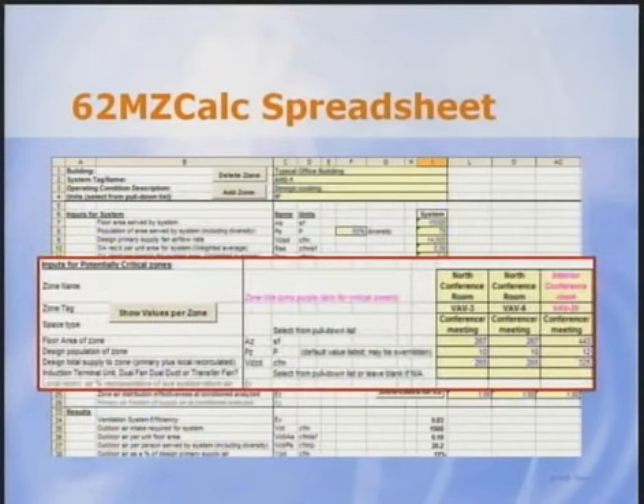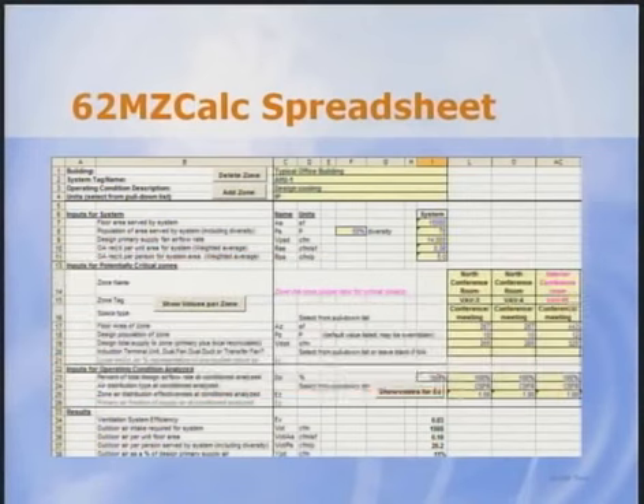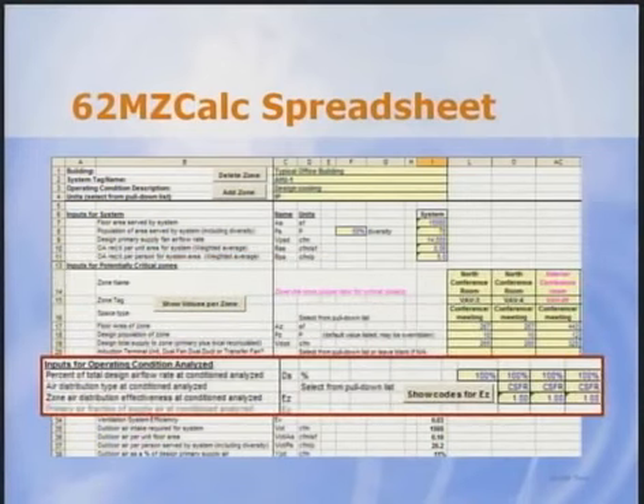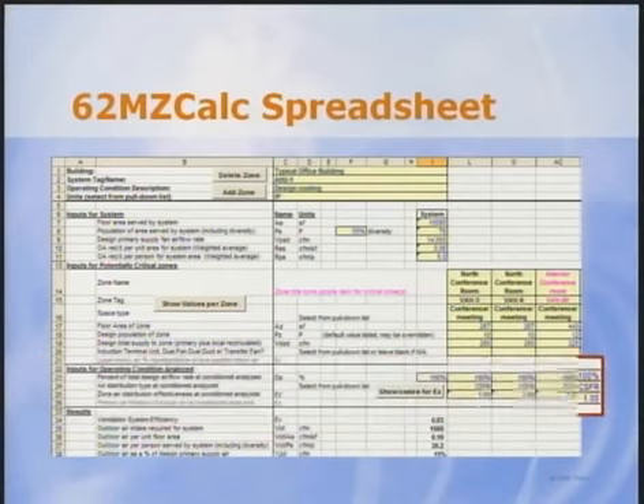Next is the zone input section. It is only necessary to enter the potentially critical zones, since the critical zone will determine the ventilation rate regardless of operating conditions at other zones. But it is usually simpler to enter every zone. That way the spreadsheet will automatically sum up system information, and I don't have to make a judgment call about which zones are maybe critical. The next section is where the user describes the system at the operating conditions being analyzed. This section allows many different conditions to be analyzed without overwriting the basic system design data in the previous section. The final section of the spreadsheet is the results section.